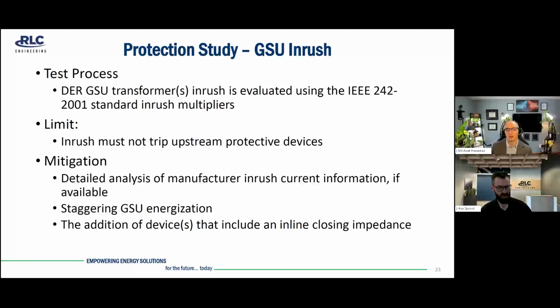And if it's not, then we might be able to look at detailed analysis of manufacturer inrush current information, if that's available. We could look at staggering GSU energization. So if you have a facility with multiple GSU transformers, if a single GSU transformer is not causing any kind of protective device coordination tripping concerns, then you might be able to look at staggering the energization of those GSUs. Or you might need to look at introducing an impedance into the closing of those GSUs to limit the inrush current.